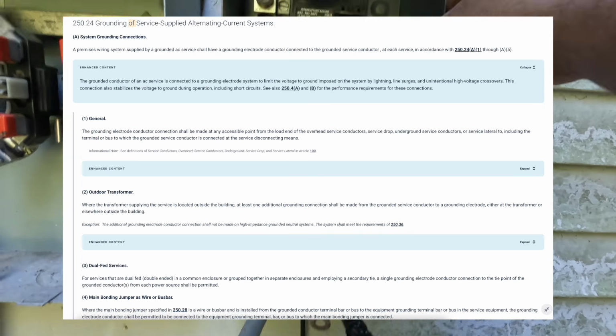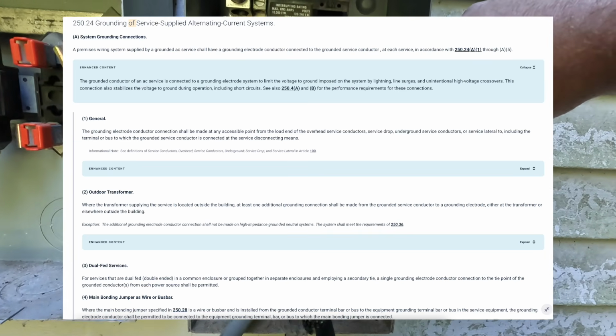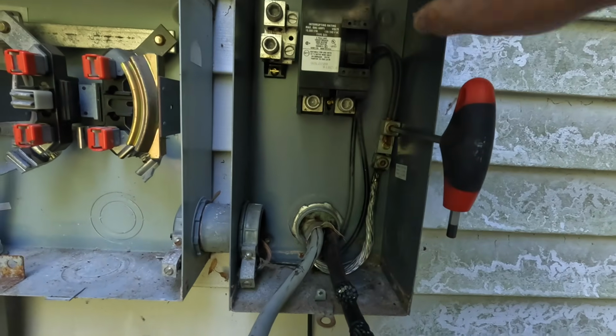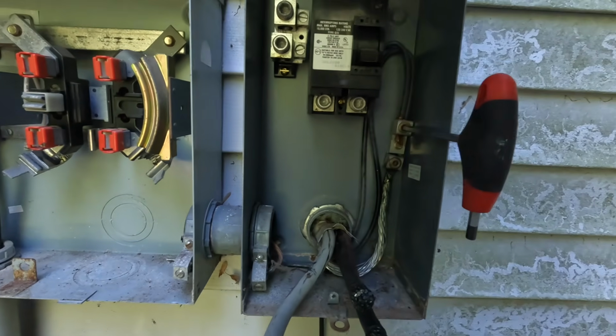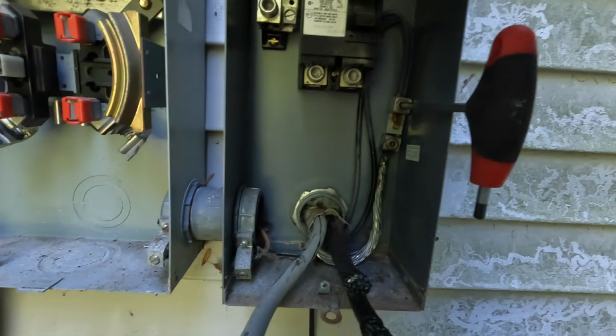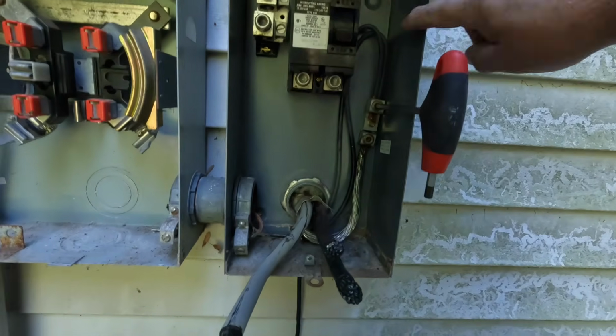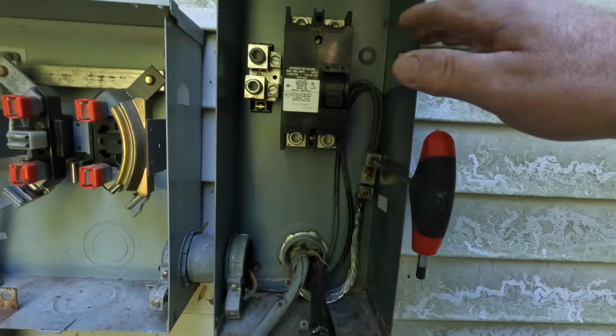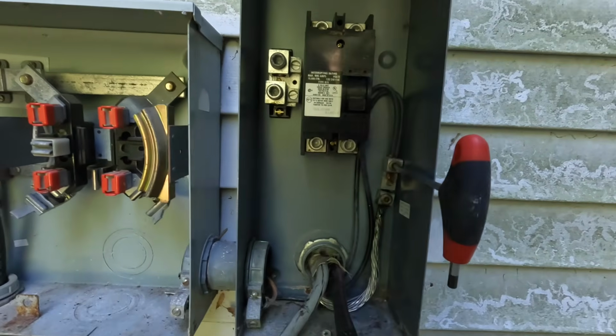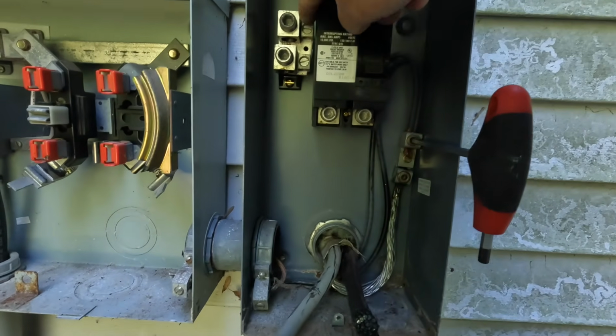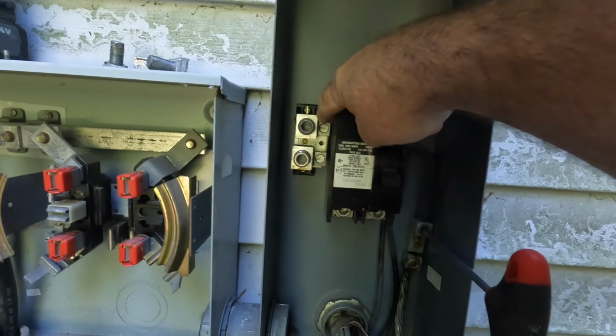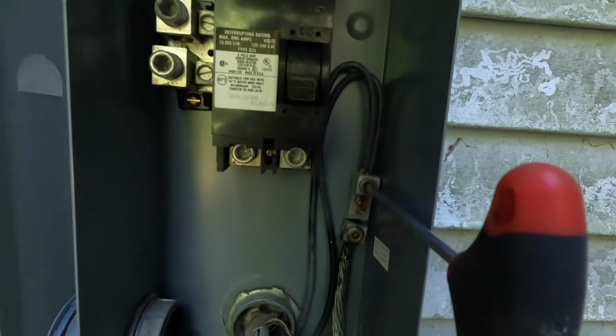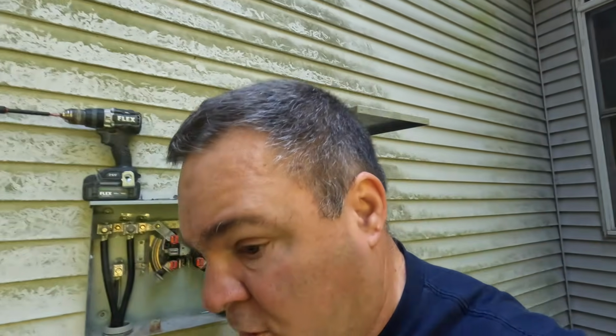because the code specifically says, well, it's an interpretation, that the grounding electrode conductors cannot use the enclosure as a raceway from your neutral to your ground. Even though it's bonded here, the main bonding jumper is in. This is where they separate from. This is where the equipment grounding conductor originates, inside this panel. But these electrodes should have been attached over here. And of course you have the terminals to do it, and they didn't do that. Instead they did a violation. Obviously everything worked out, but there's reasons why we have the codes the way they are.